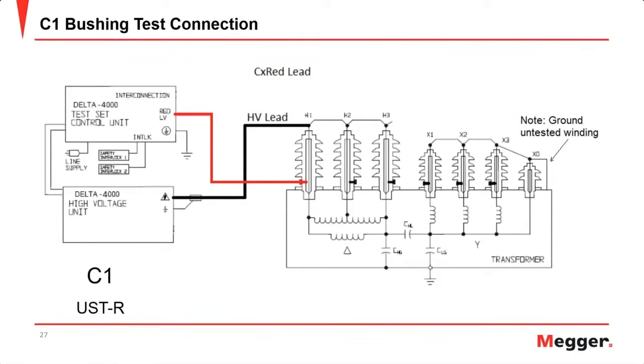All of the secondary bushings are shorted together, including an extra connection to ground. For whichever winding we're not testing the bushings on, we do want to connect that to ground to remove any possible influence from those bushings. And then we will take off the cover of the test tap and connect our red measurement lead. Now, it's very important to note that while you are doing bushing tests, you should only have one bushing tap uncovered before you start the test.